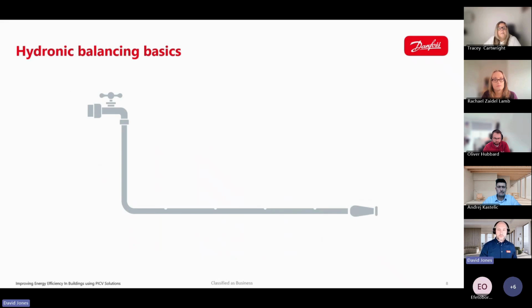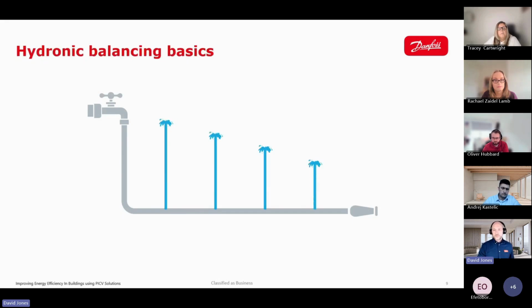So if we run through the animation, we can see how water behaves under different demands and balancing techniques. Here we have our water hose with 4 holes as outlets, all the same size. Once we introduce flow through the hose, which represents our system, we can see straight away that because water is essentially lazy and always takes the path of least resistance, we have a higher flow rate through the nearest hole here, which we could think of as a heat emitter, but the flow reduces further along the hose or branch as it travels.